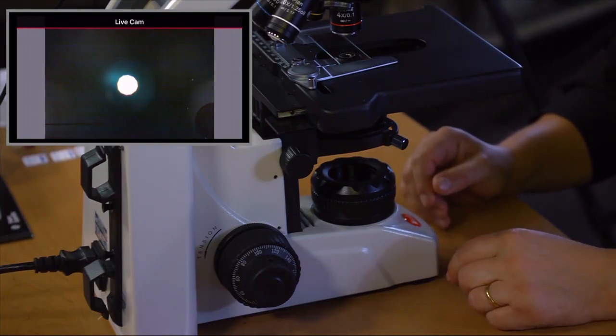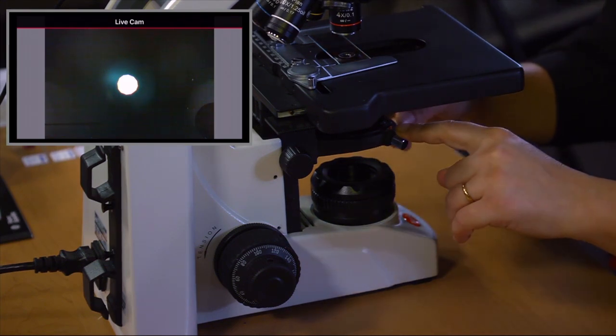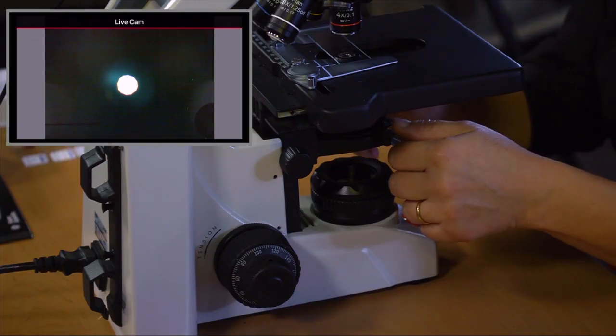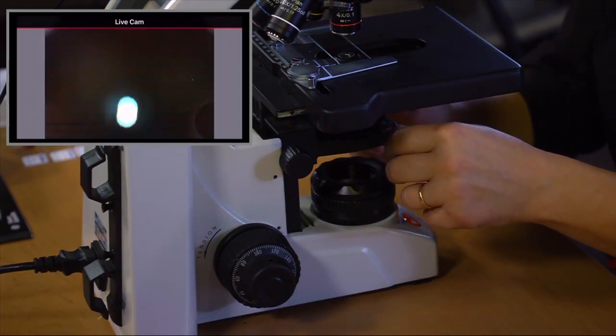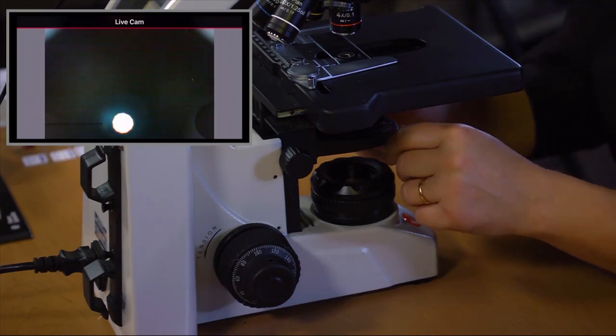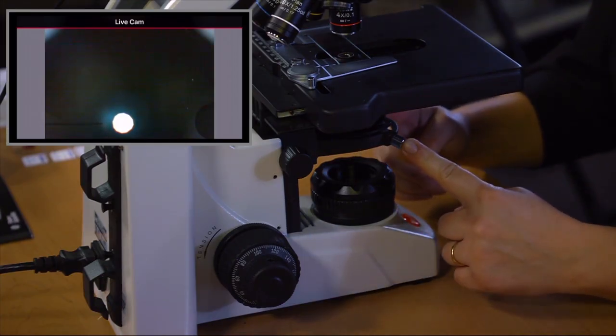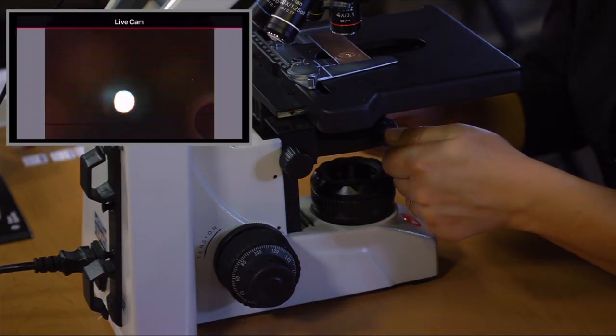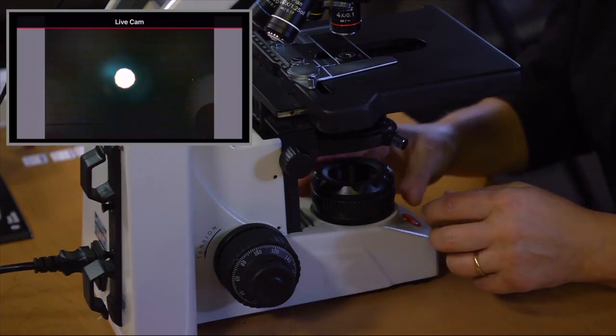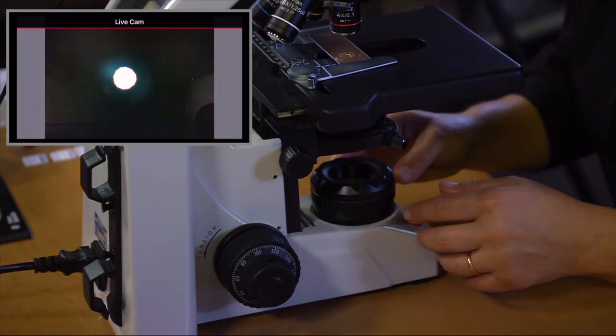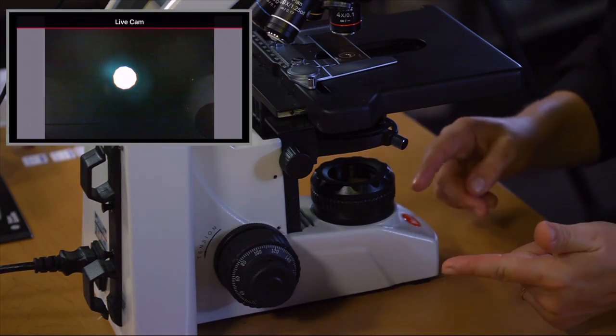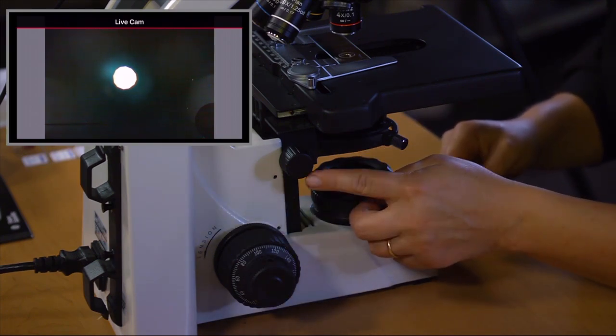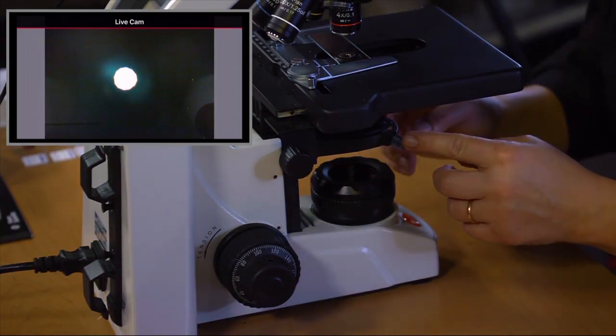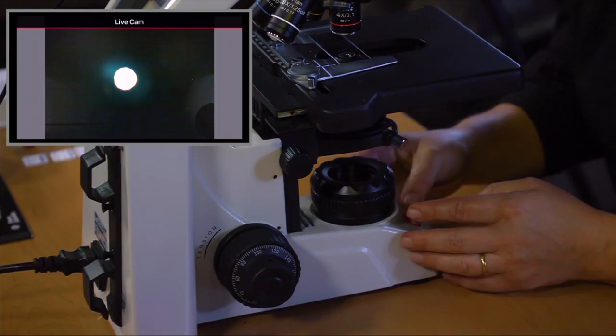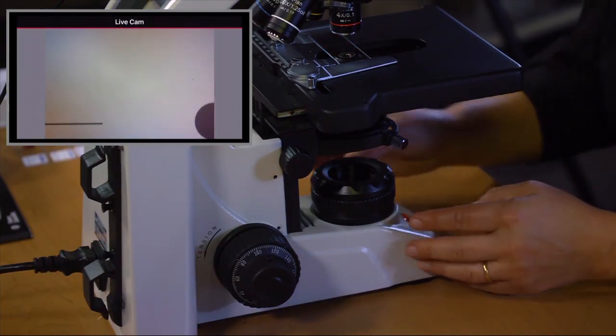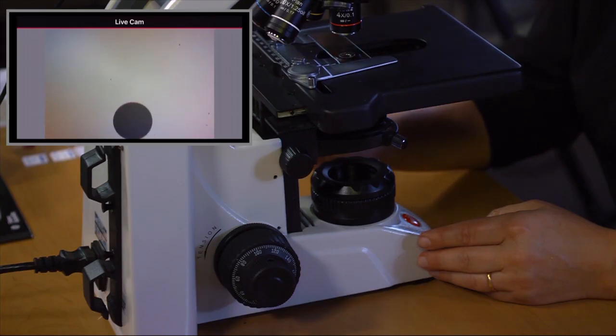The second part of the Köhler process is you want to make sure that your light beam is right in the middle of your image. Sometimes your light is not in the center. So you have to use the two buttons on the side underneath your stage and move your circle into the middle of your field of view. It should be right in the middle. Again, it should be focused on your specimen. You should close the field diaphragm. You need to make sure your condenser is at the right height where you can see the octagon, and it has to be in the middle. Once you have all this set up, you can increase your field diaphragm and you can start the art of microscopy.